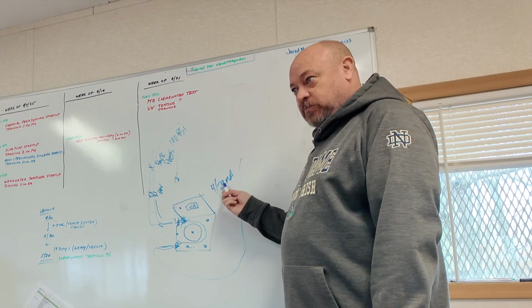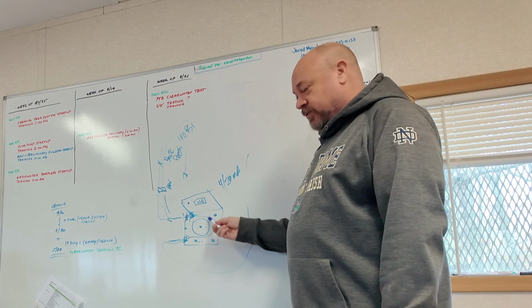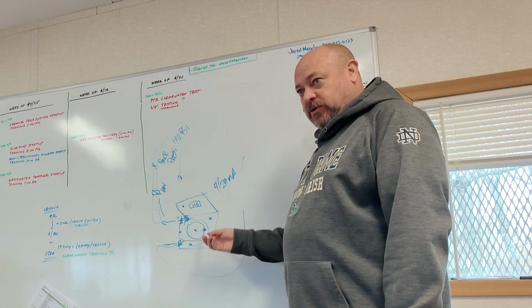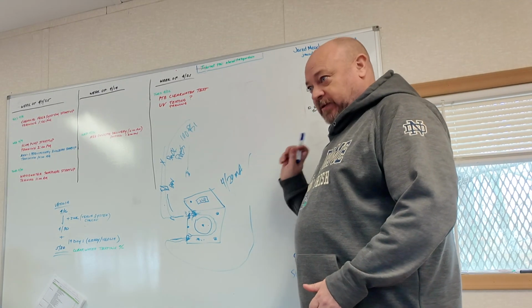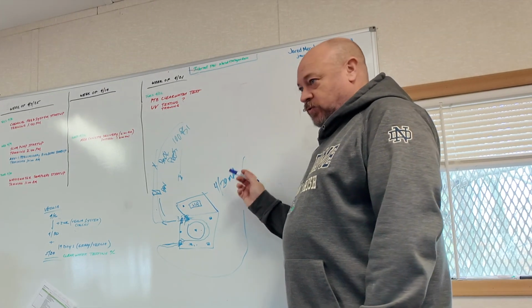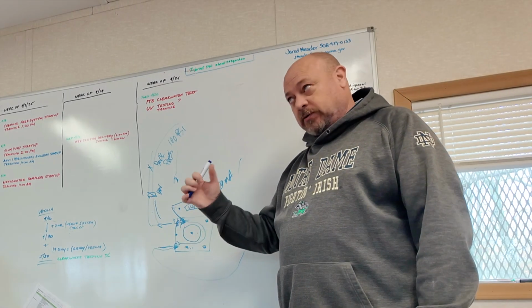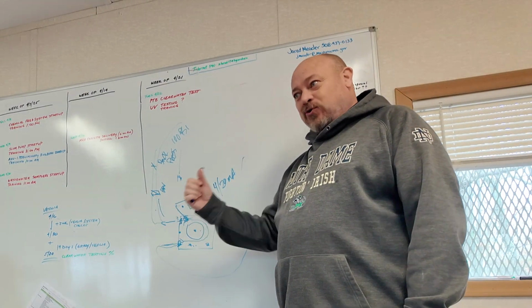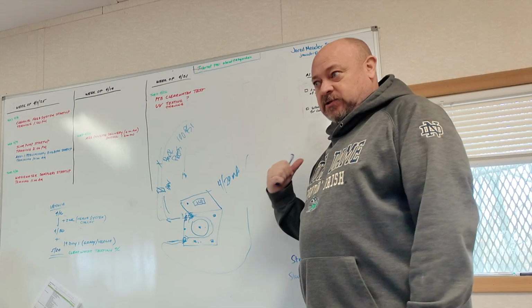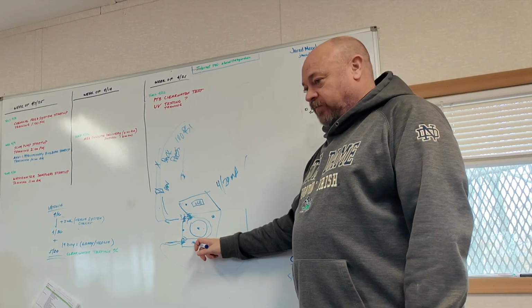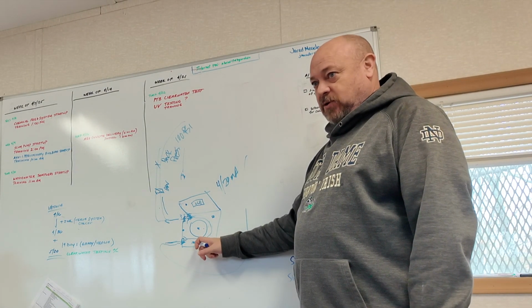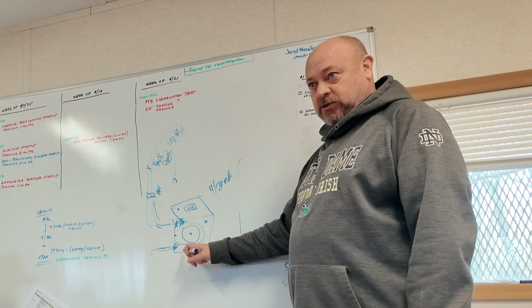So 4 to 20 is your flow pacing signal, telling the pump how fast to run, and then your start-stop is telling the pump to turn on, turn off. Pump has 4 to 20 output feedback to the SCADA system, so if you're sending it a 12 milliamp signal for 50%, you're going to be seeing a 12 milliamp signal, 50% speed feedback. It also has the default for the leak detection, so if at any time you have a leak in there, you'll trigger the leak detection and shut the pump off.